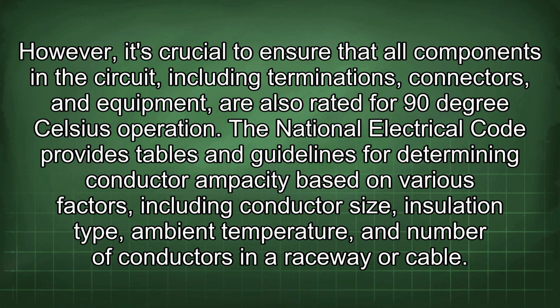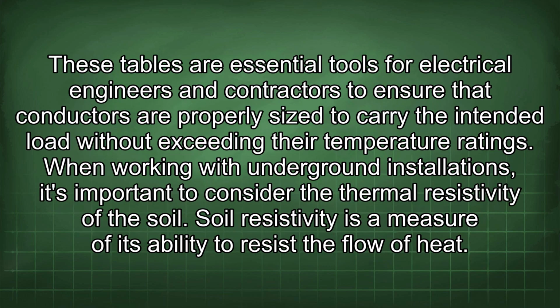90 degrees Celsius operation. The National Electrical Code provides tables and guidelines for determining conductor ampacity based on various factors, including conductor size, insulation type, ambient temperature, and number of conductors in a raceway or cable. These tables are essential tools for electrical engineers and contractors to ensure that conductors are properly sized to carry the intended load without exceeding their temperature ratings.